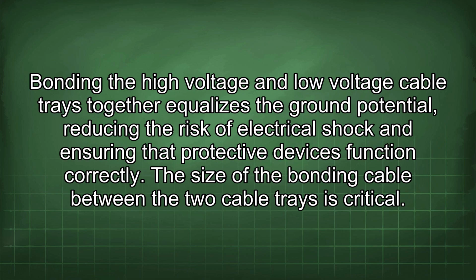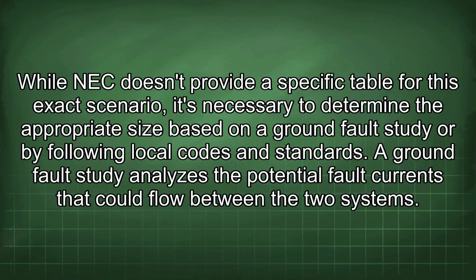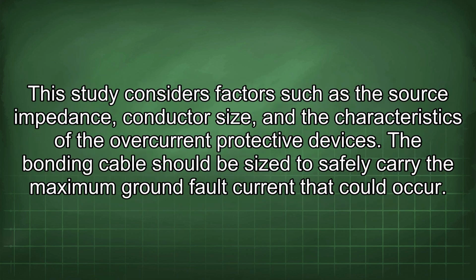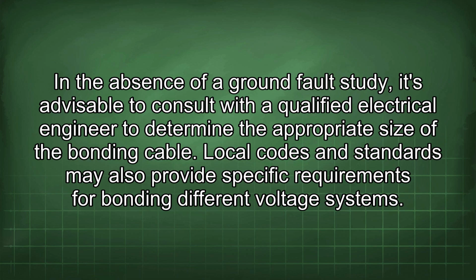The size of the bonding cable between the two cable trays is critical. While the NEC doesn't provide a specific table for this exact scenario, it's necessary to determine the appropriate size based on a ground fault study or by following local codes and standards. A ground fault study analyzes the potential fault currents that could flow between the two systems. This study considers factors such as the source impedance, conductor size, and the characteristics of the overcurrent protective devices. The bonding cable should be sized to safely carry the maximum ground fault current that could occur. In the absence of a ground fault study, it's advisable to consult with a qualified electrical engineer to determine the appropriate size of the bonding cable.